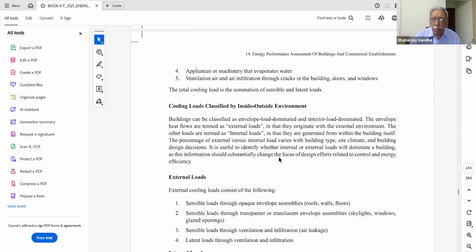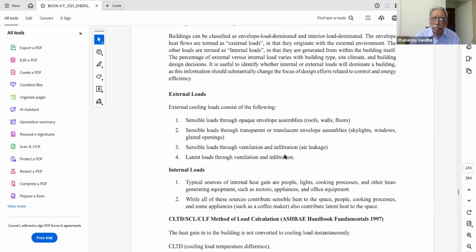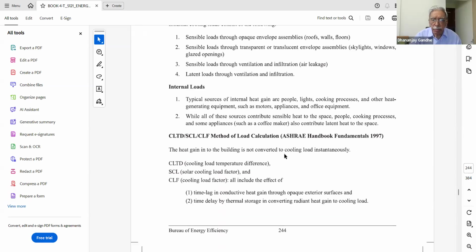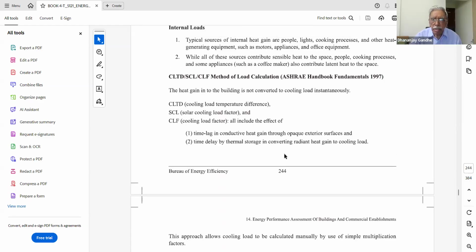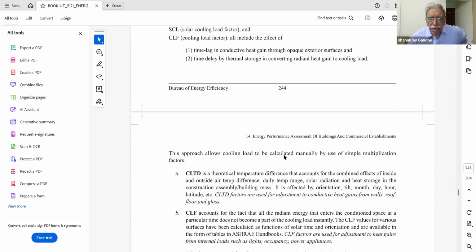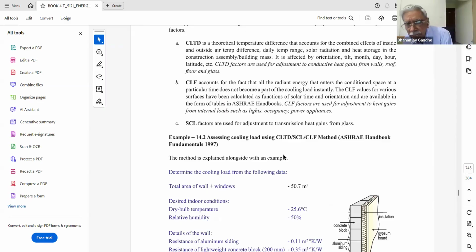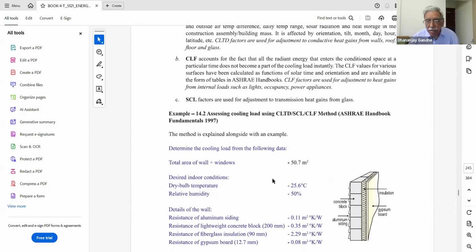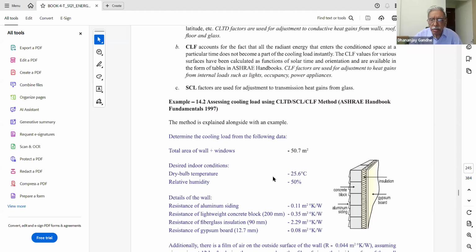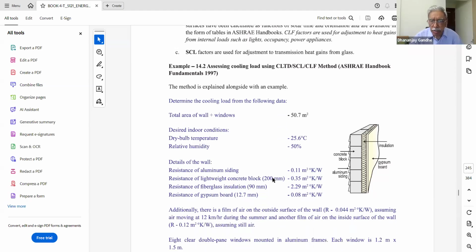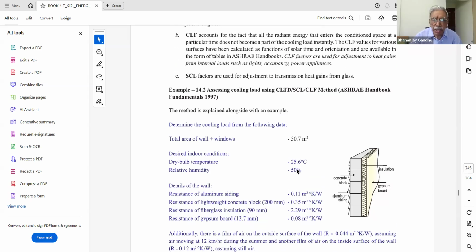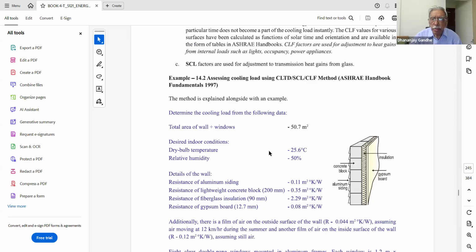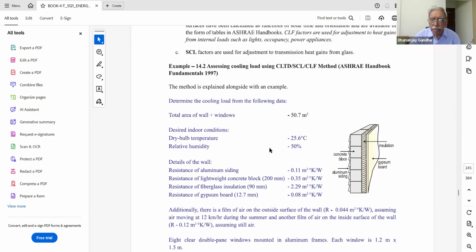And then we have also seen the heat load calculation. One is from the external loads and one is from the internal heat loads. So segregation of loads is done that way. And then various factors like CLTD, SCL, CLF are calculated. They are taken from the ASHRAE handbook. Okay. So then we proceeded to see what calculations are to be done. First of all, calculation of the heat load, which is given not in terms of thermal units, but in terms of watts. Load is calculated. So first we saw the cooling load calculations by using the ASHRAE method.